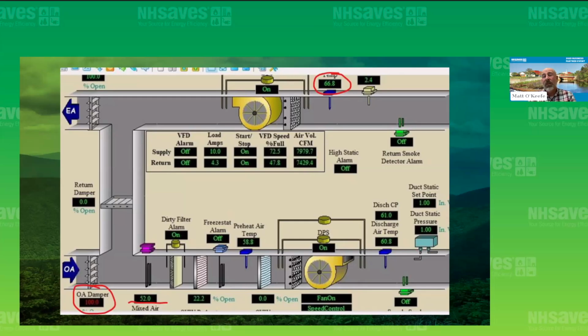And then it also leads to other things that could be damaging to the customer site, where if that damper is disabled open and it doesn't have a freezestat that is working properly, when temperatures get colder than 50 degrees outside, coils can freeze, and that's a much more expensive repair that customers are commonly having to deal with.